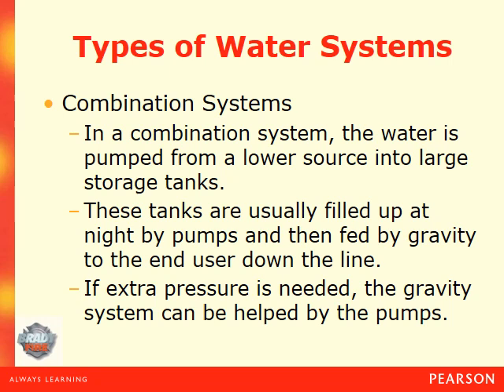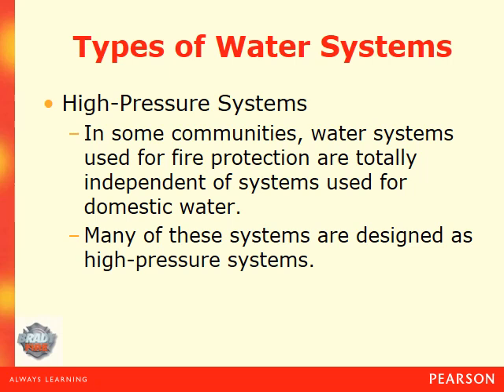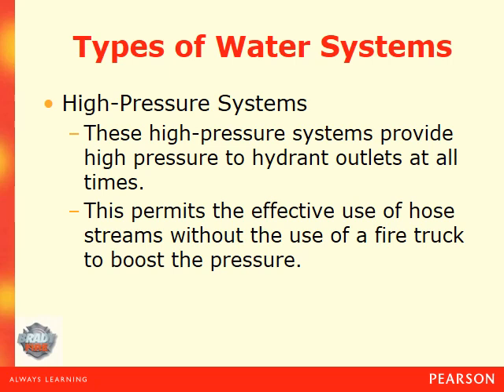If extra pressure is needed, the gravity system can be helped by the pumps. In some communities, water systems used for fire protection are totally independent systems from the domestic water supply. Many of these systems are designed as high pressure systems, providing high pressure at hydrant outlets at all times, permitting effective use of hose streams without a fire truck to boost the pressure. It's important to know that these systems are totally separate from the drinking water — a lot of times these systems also use non-potable water because their primary use is for firefighting.